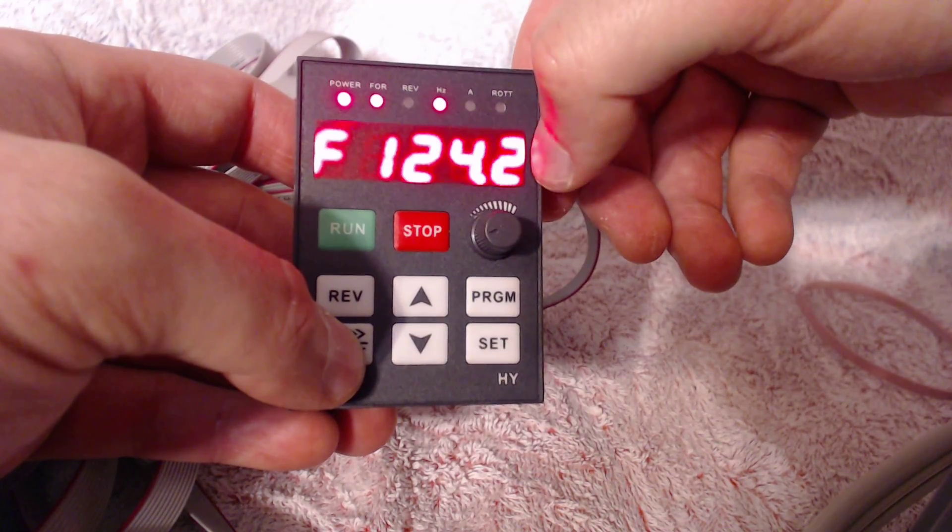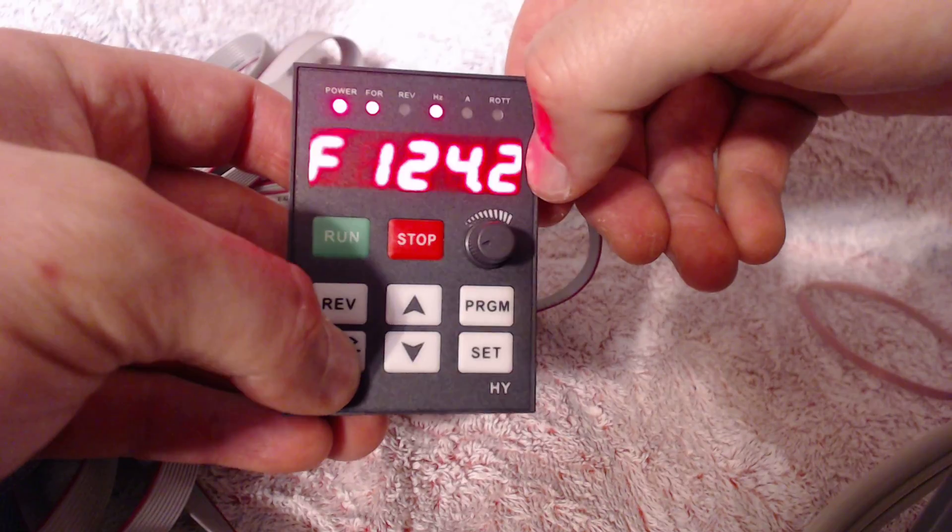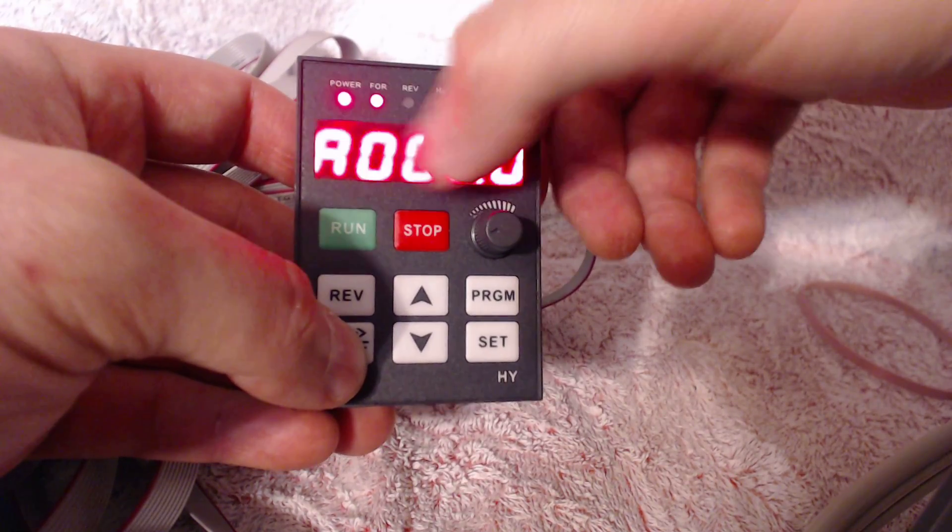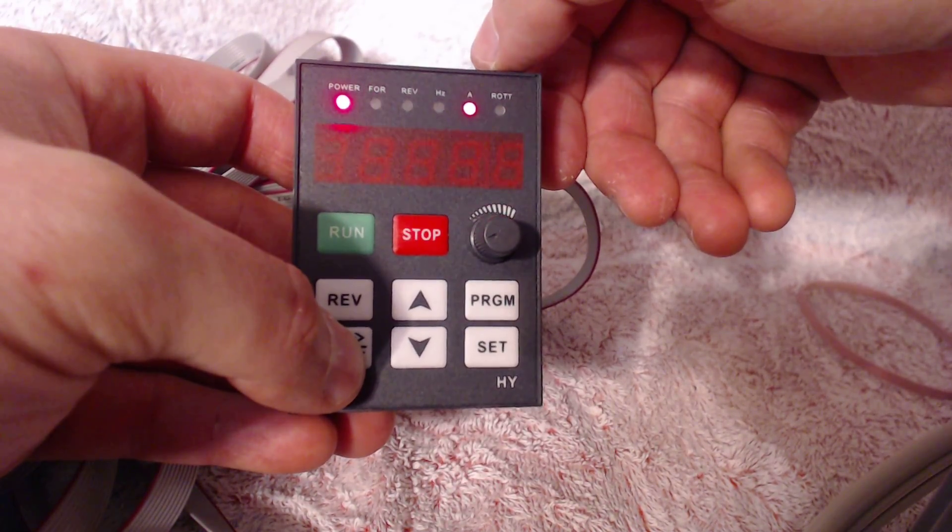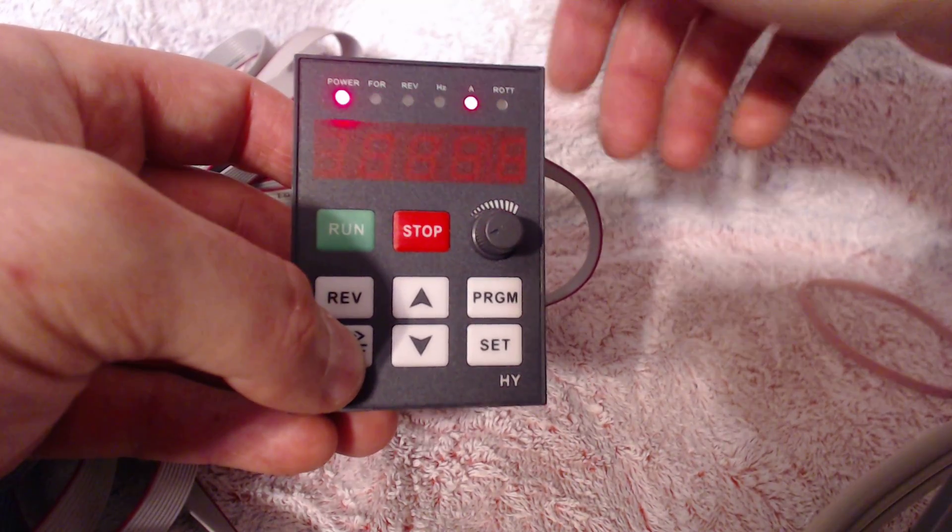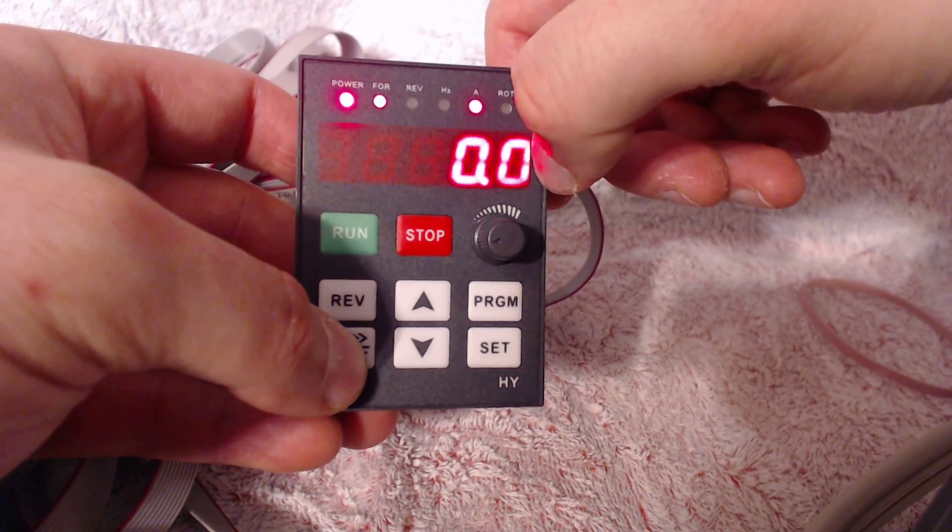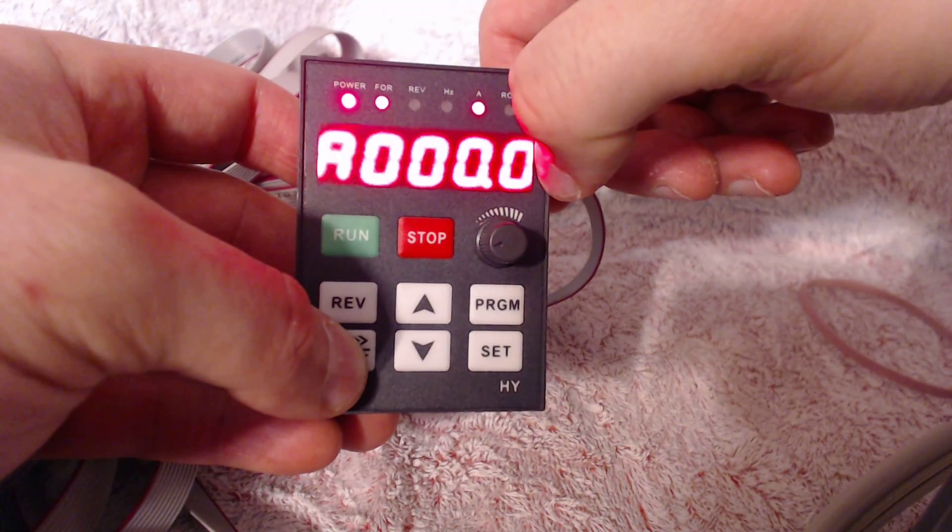ROT stands for rotation. You can switch the units from hertz to actual RPM. And a lot of guys like RPM. This unit is already set to reflect RPM, being there's no motor hooked up. We're not going to see that. But if you hit shift, now we're searching and right now we're on frequency. We can see our hertz. It's lit. And you can see 124 and she's moving a little bit. As I go through it, now you see amps. And you see zero because, of course, we have no motor attached. When you attach a motor, guys, you'll typically see anywhere, if there's no load, 1.6, 1.5. I've seen them as low as 1.1. It just depends on where you're at. Overall, if you see an abnormal amp condition, pay very close attention to that.